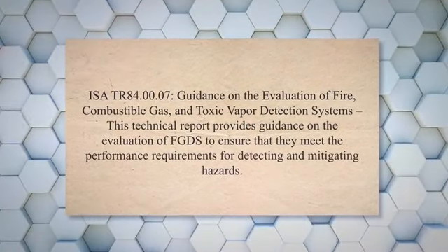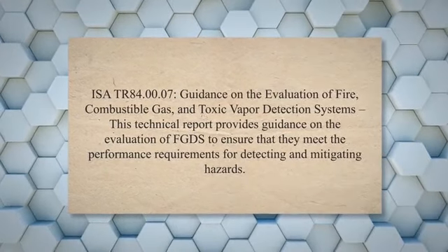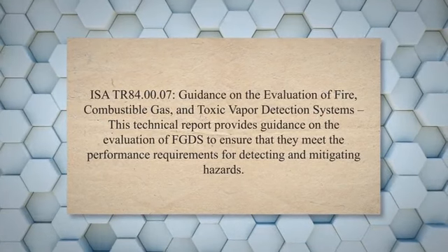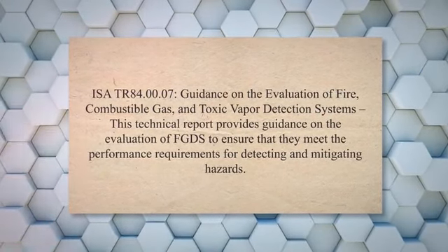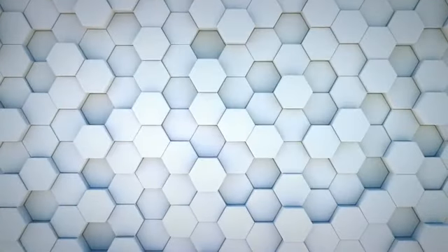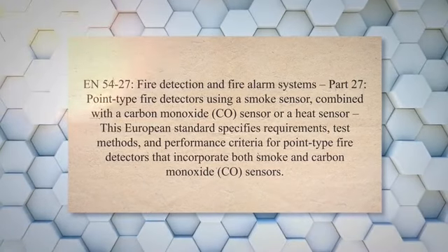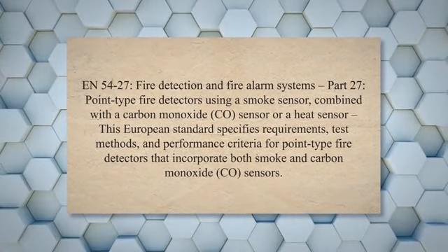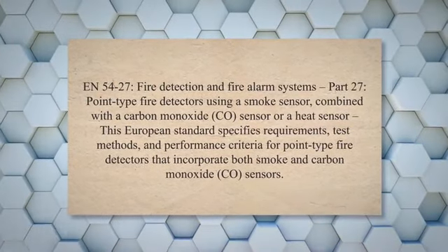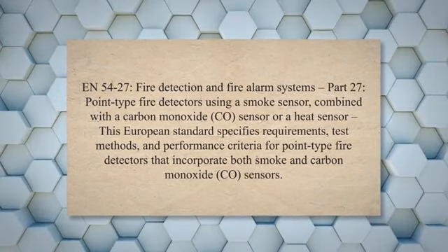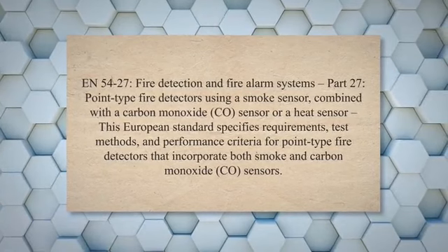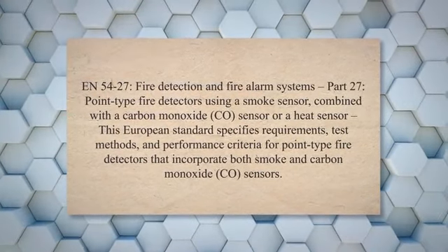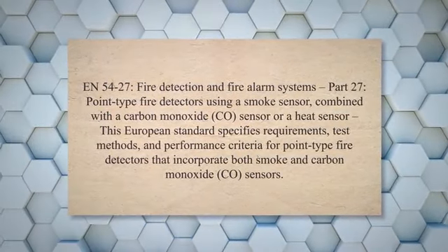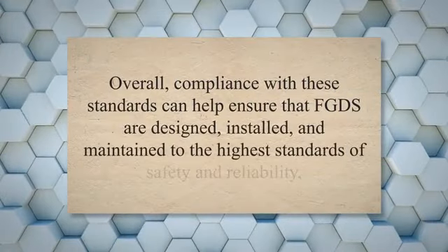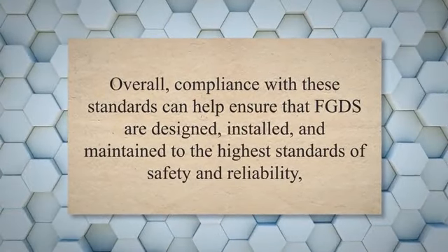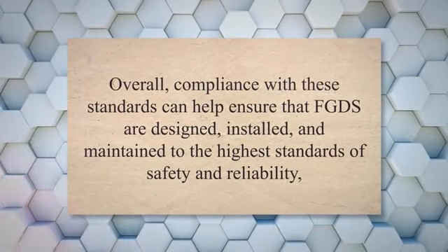ISA TR 84.00.07, Guidance on the Evaluation of Fire, Combustible Gas, and Toxic Vapor Detection Systems. This technical report provides guidance on the evaluation of FGDS to ensure that they meet the performance requirements for detecting and mitigating hazards. EN 54-27, Fire Detection and Fire Alarm Systems. Part 27, Point Type Fire Detectors using a smoke sensor, combined with a carbon monoxide (CO) sensor or a heat sensor. This European standard specifies requirements, test methods, and performance criteria for point-type fire detectors that incorporate both smoke and carbon monoxide (CO) sensors. Overall, compliance with these standards can help ensure that FGDS are designed, installed, and maintained to the highest standards of safety and reliability.